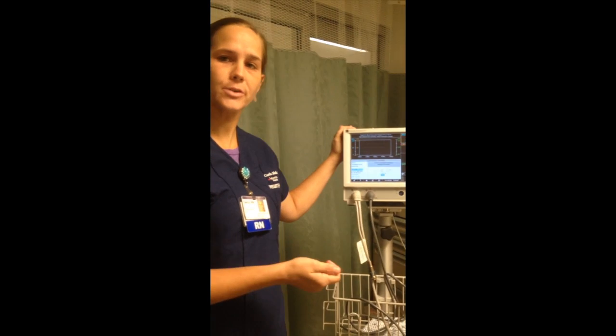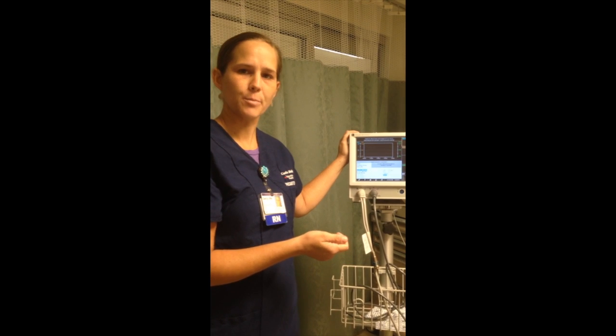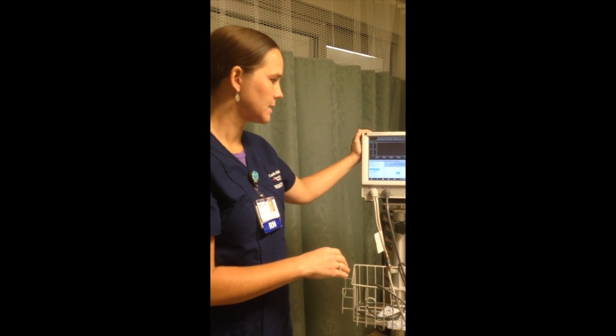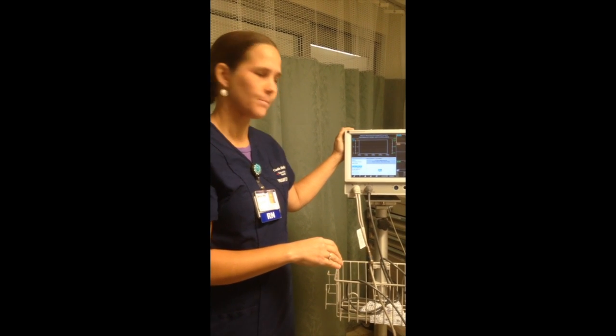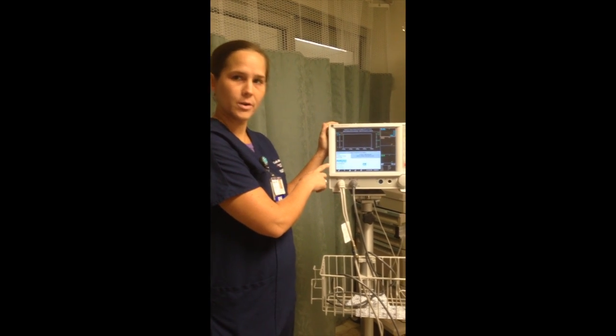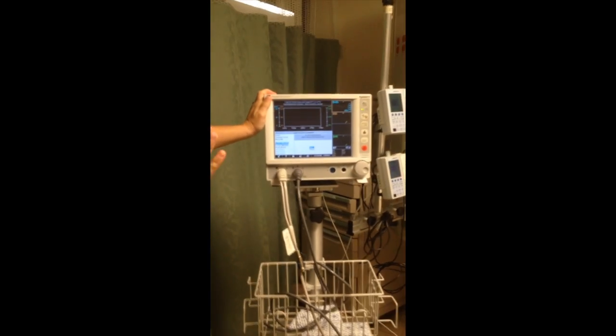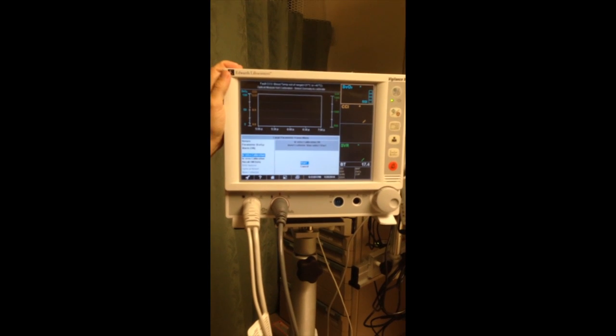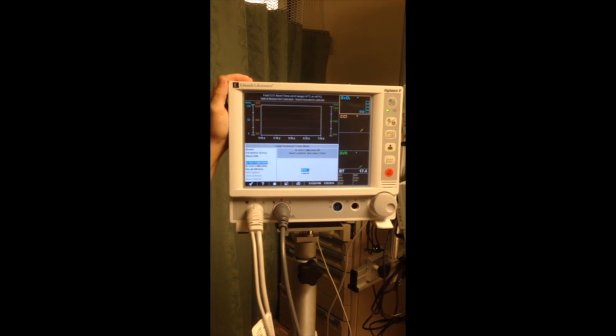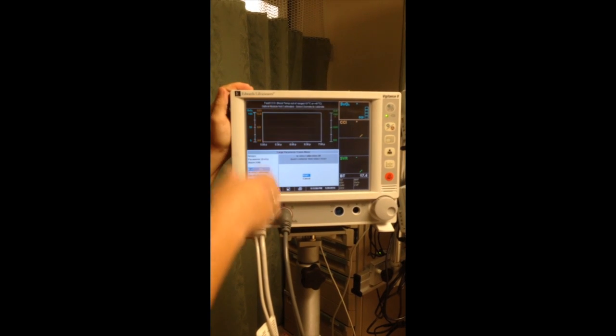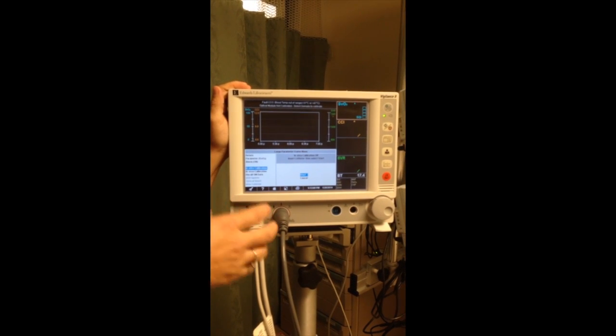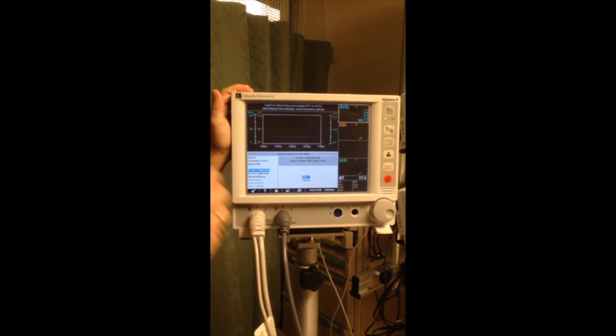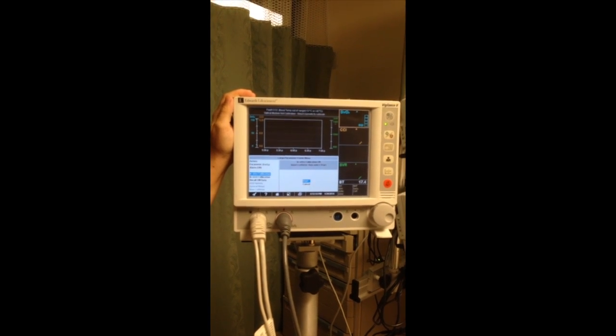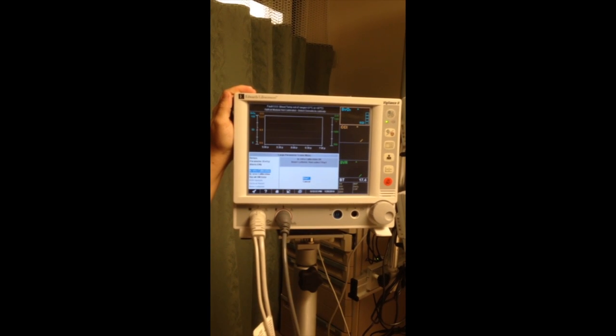Once the Swan is inserted, you can do an in vivo calibration, which is inside the body. It's actually a bit more accurate, and we should be recalibrating daily, usually with AM labs. To do the in vivo calibration, it's the same steps, but you go to in vivo, and when you push calibrate, it will ask you to draw. At that point, you draw an SVO2, ask the RT to run it, and you come in and put your lab values. When it asks you to draw, it actually holds those values so that it puts the values of the labs back into the machine at the exact time of all the other numbers to do its calculations.